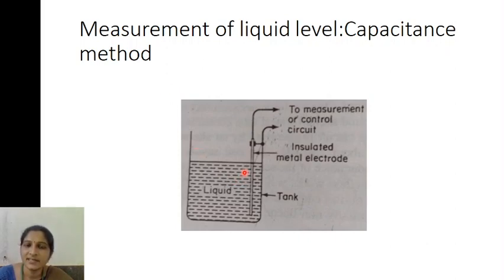If there is any liquid level change, either increase or decrease, there is a change in capacitance, so that you can measure the capacitance. The advantage of this capacitance method is that it has no moving parts, so there is no wear and tear of the instrument. The disadvantage of this capacitance method is temperature. If the temperature changes, it affects the capacitance, and that affects the liquid level measurement. That is one of the disadvantages of this method.